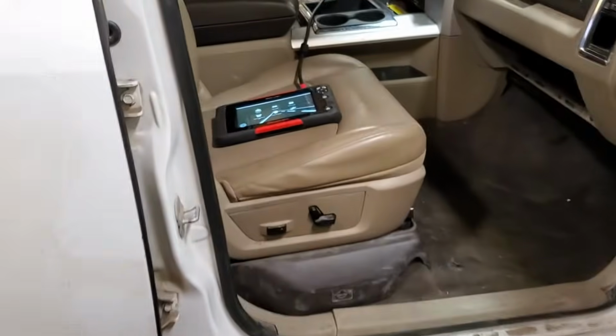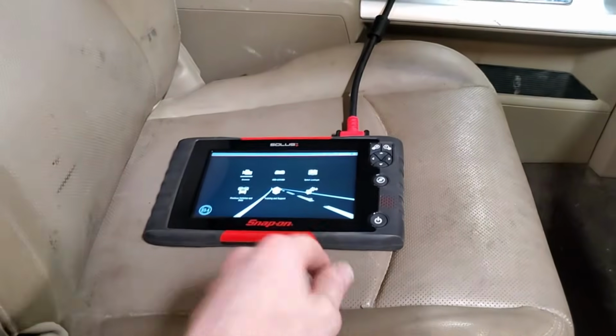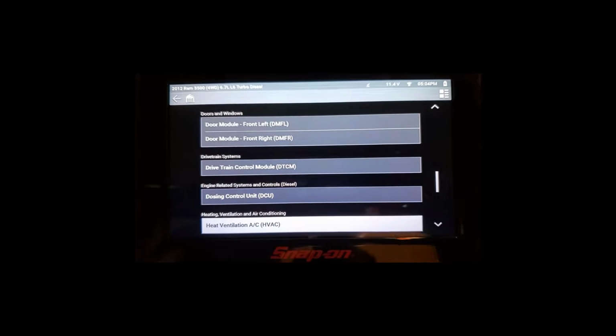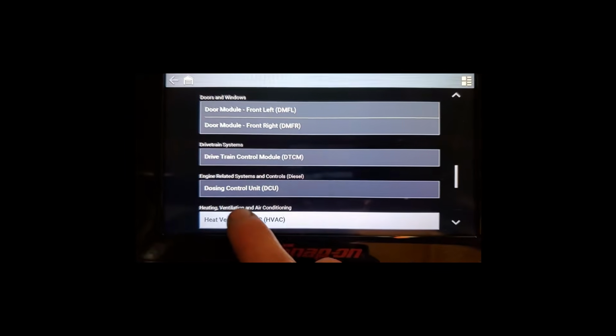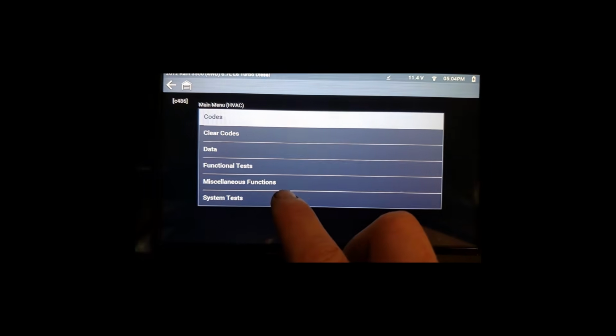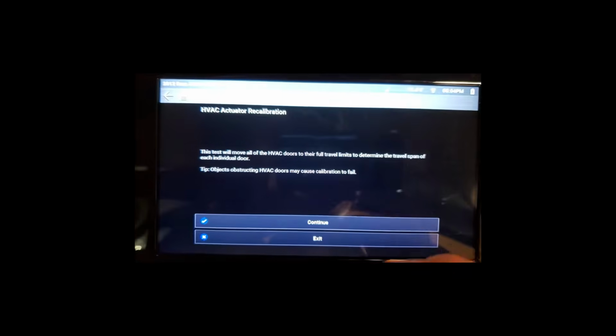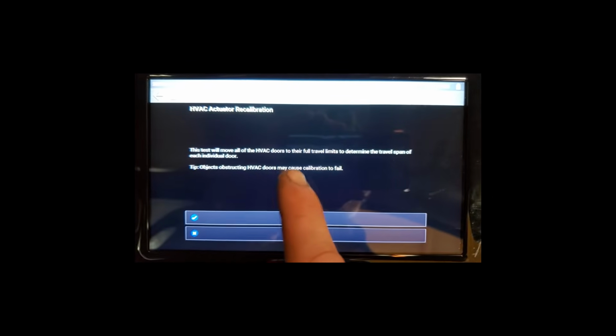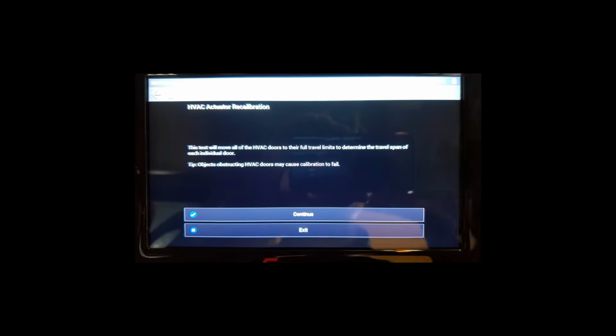Now I'm going to show you the actuator recalibration procedure with this snap-on scanner. So to recalibrate the actuators, you have to go into the heating, ventilation, and air conditioning module, and it's going to be under system test, at least with a snap-on scanner. Actuator recalibration — it says here it's going to test all the doors to their full travel limits. Continue.